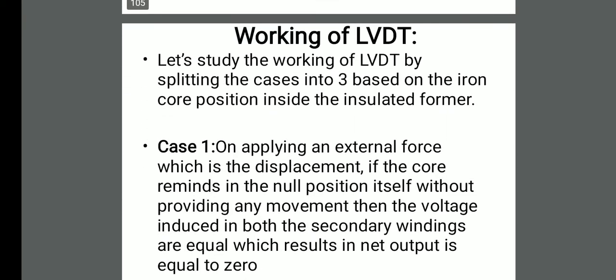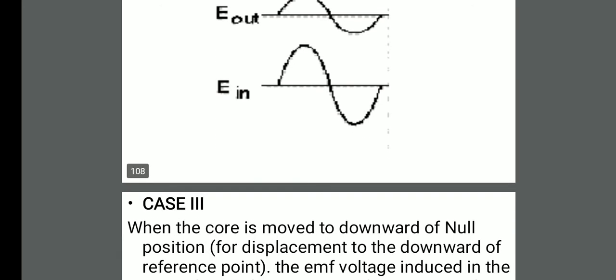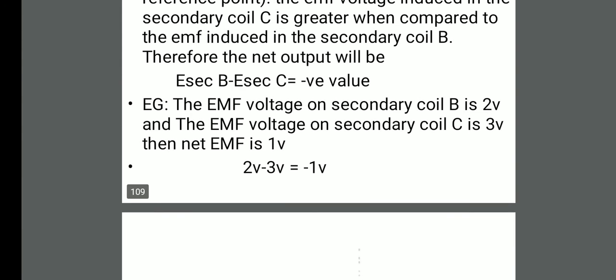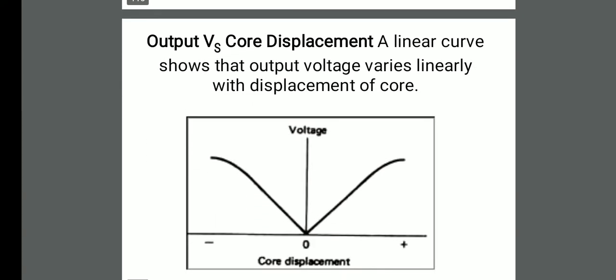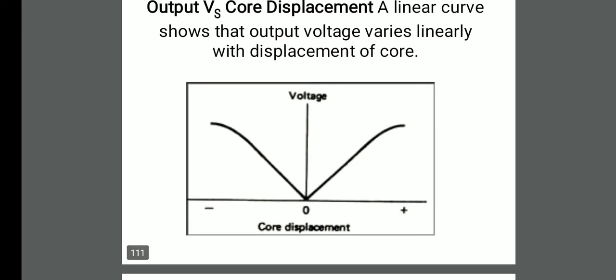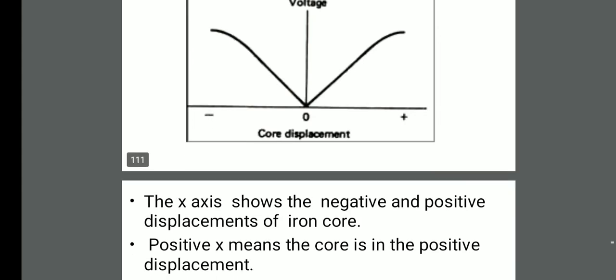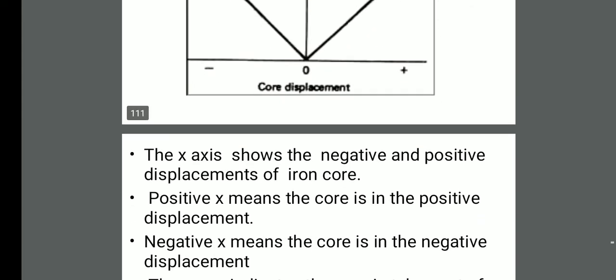That is how the LVDT works across three cases, each giving a different output. The LVDT can be used to measure displacement at a reference point. Looking at the output versus core displacement characteristics of an LVDT, the linear curve shows that output voltage varies linearly with displacement. The Y-axis shows voltage and the X-axis shows core displacement in both positive and negative directions. As the core displaces, the voltage increases in a linear way on both positive and negative sides. Positive X means the core is moving upward; negative X means the core is moving downward.